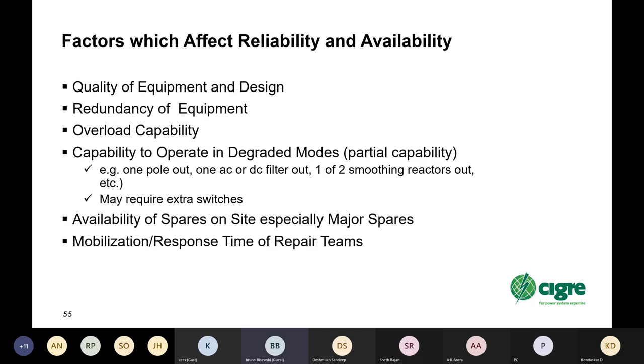So what are the factors which affect reliability and availability? Well, first one, of course, is quality of the equipment and design, redundancy of equipment, overload capability, the capability to operate in degraded modes, which gives you partial capability. For instance, either with one pole out, AC or DC filter in or out, outage of one of two smoothing reactors, etc. It may require additional extra switches or extra equipment to be able to operate in the degraded modes, but it may be worthwhile, so you should consider that when you're doing your specification.